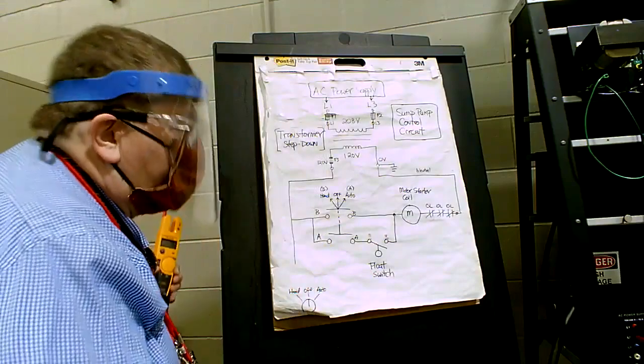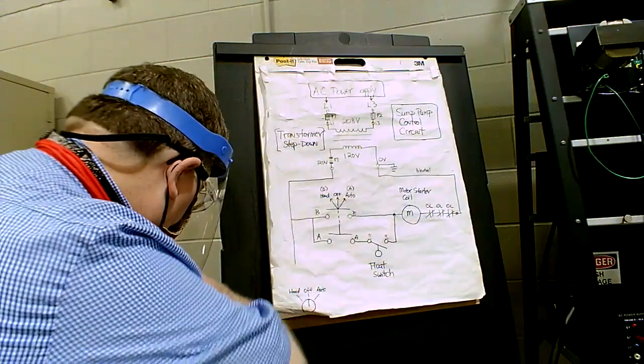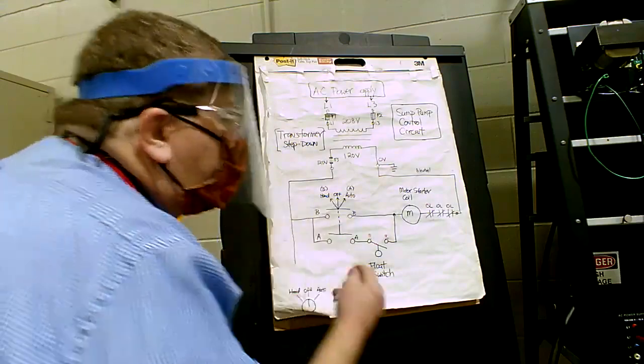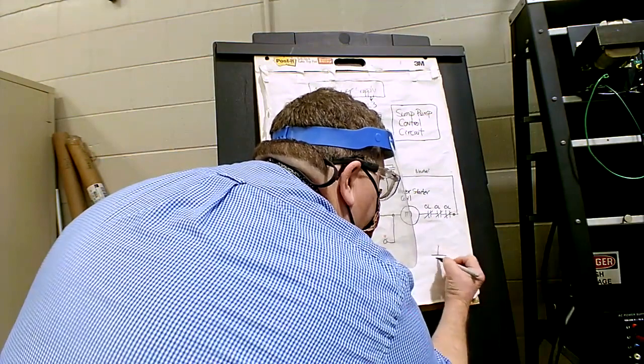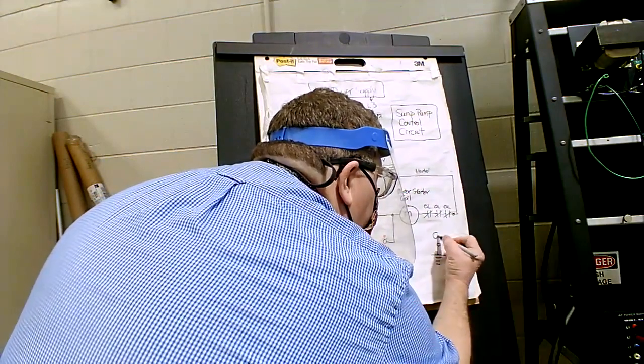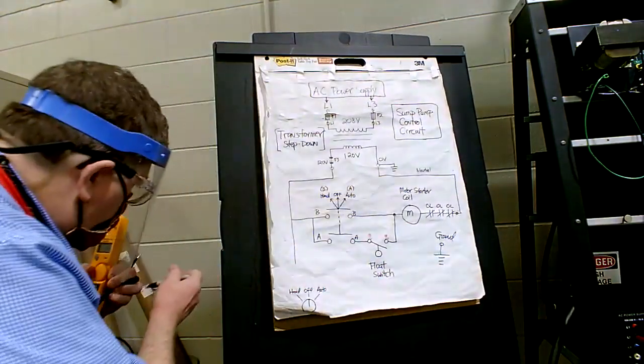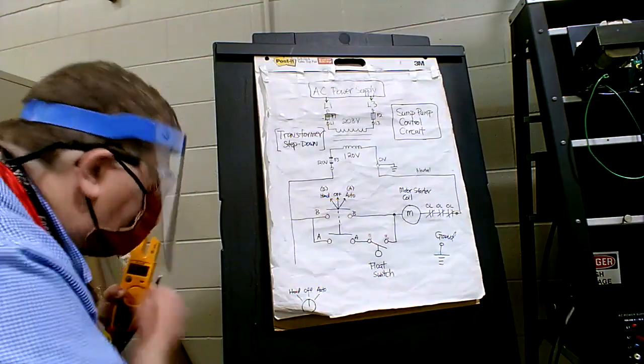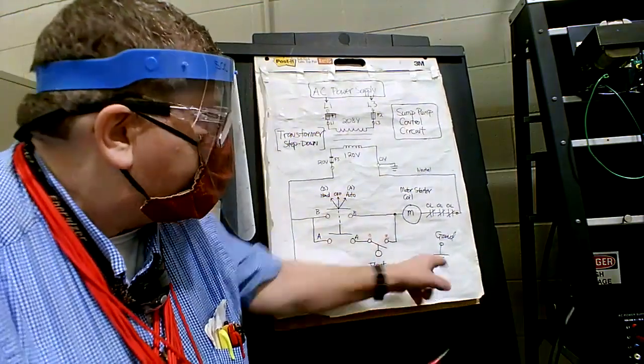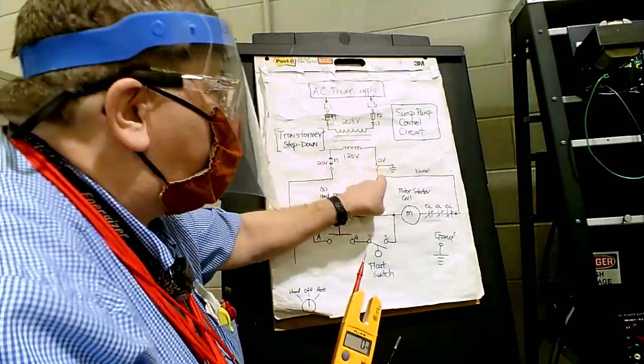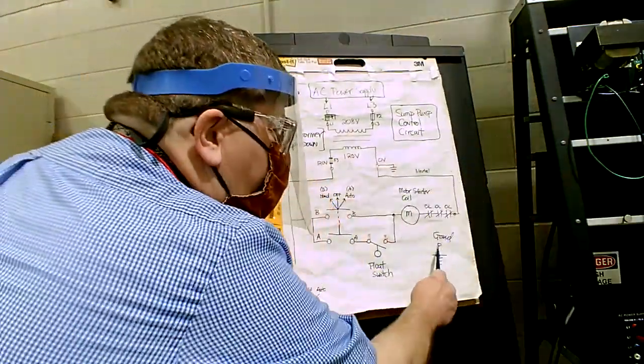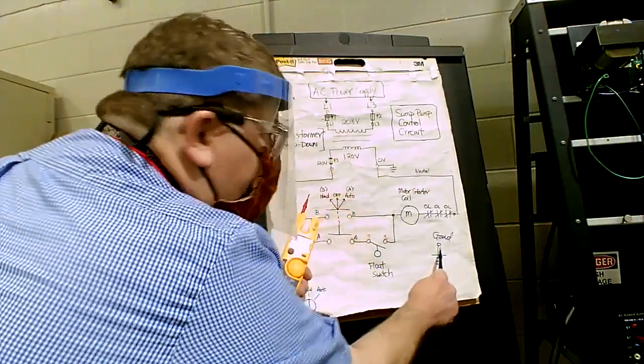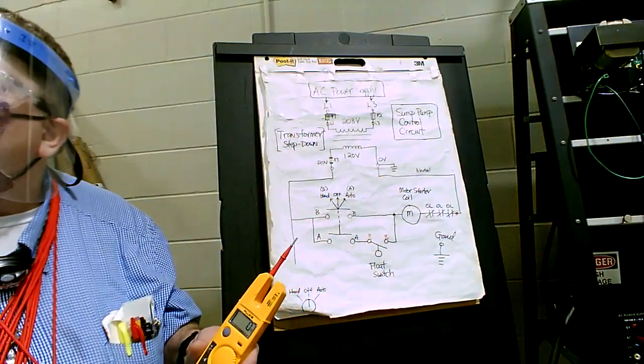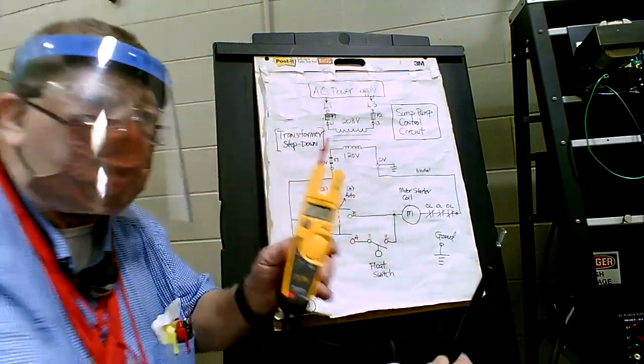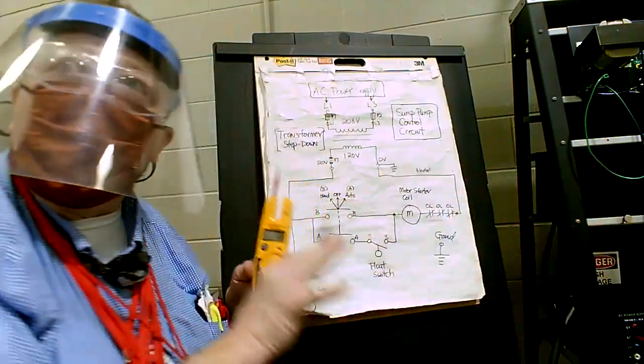Now, let's say, for instance, I had a different grounding point out here. I've got a different ground point, but it is a ground point. If I've got the neutral grounded, that means I can actually put this lead out here on any ground, any actual ground, and still get good readings on my meter. Everybody understand that? As long as the neutral is grounded, then you can use for your reference on the meter any grounded point in the control panel anywhere.